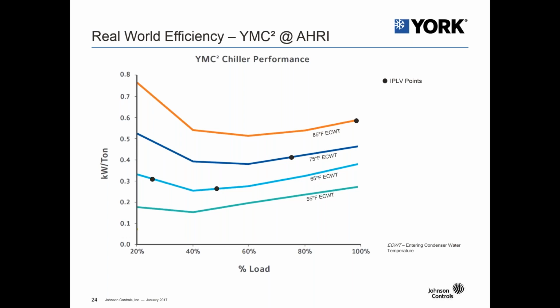So as you can see, while this is a meaningful metric to compare like-for-like chiller technologies from an efficiency standpoint, it really doesn't represent the true efficiency capabilities of a chiller. If you're able to utilize lower entering condenser water temperature, you'll see much different results in the chiller efficiency and the system efficiency.